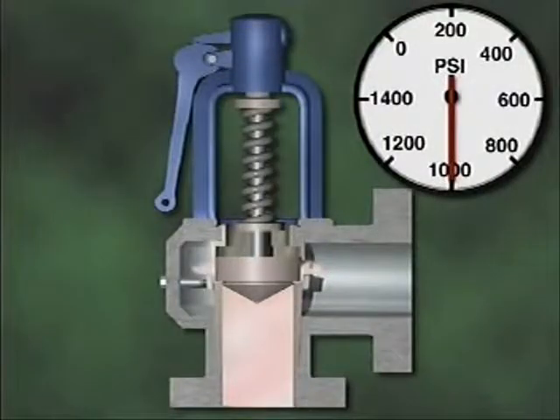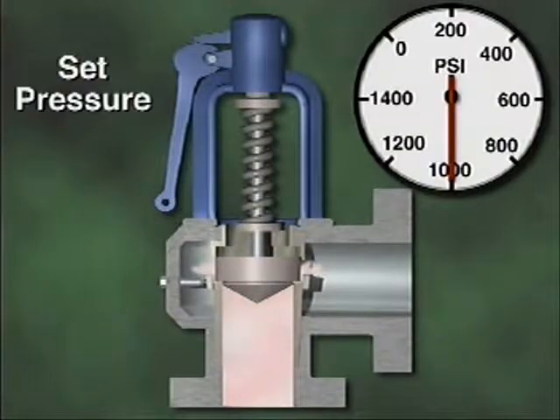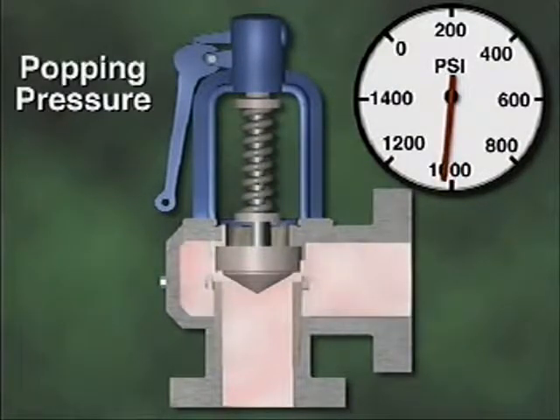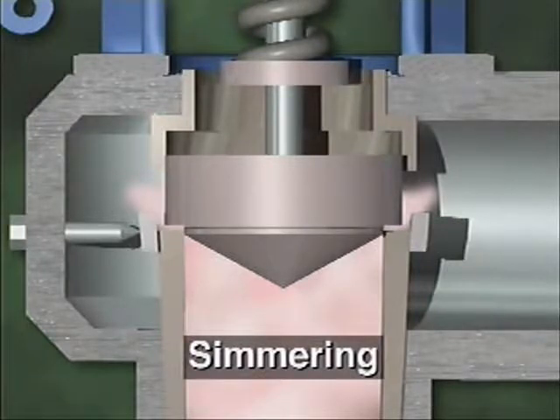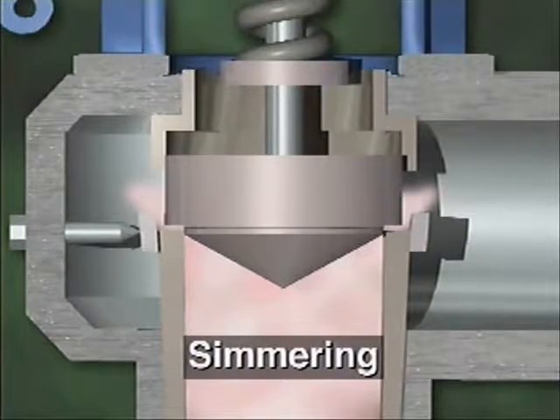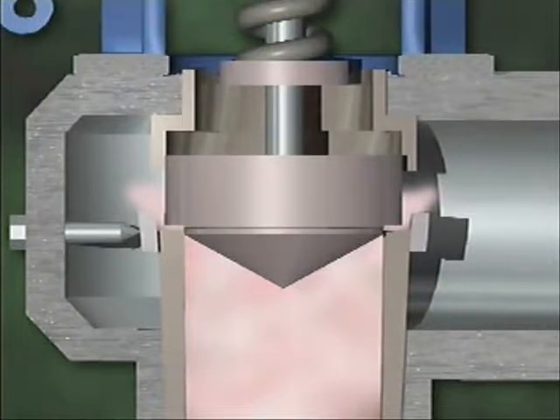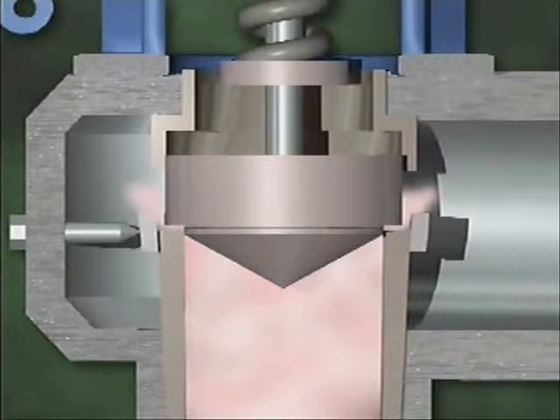The pressure at which the valve's disc begins to lift off the seat is called the valve's set pressure. The pressure at which the valve actually pops open is the popping pressure. In most cases, simmering occurs briefly before a safety valve opens fully. During simmering, the disc is only slightly lifted and the valve discharges a small amount of fluid. Simmering lasts for only a fraction of a second until system pressure acts on the lip of the disc.